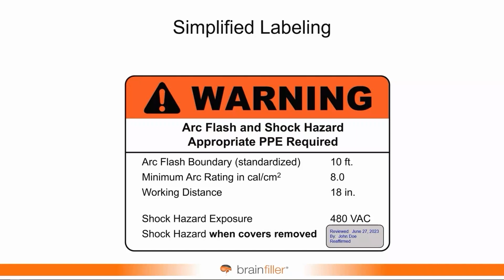What's really nice about this is when you go back and perform the review of the arc flash study, what you're really doing now is treating it like a short circuit study. As long as the calculated arc flash boundary is still less than 10 feet, as long as the 8-calorie or whatever you have listed arc rating is still sufficient, you're good to go. You could place a maintenance sticker on it that just acknowledges, yes, this has been reviewed. It is still current.